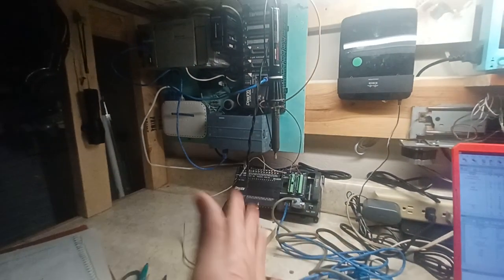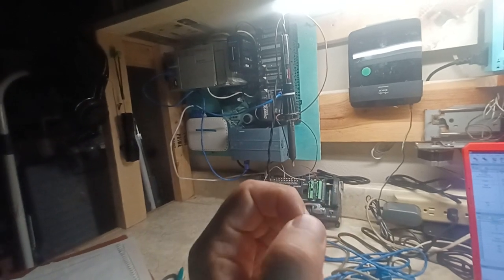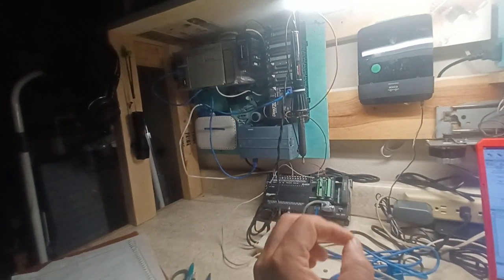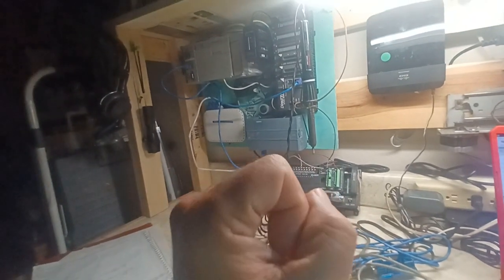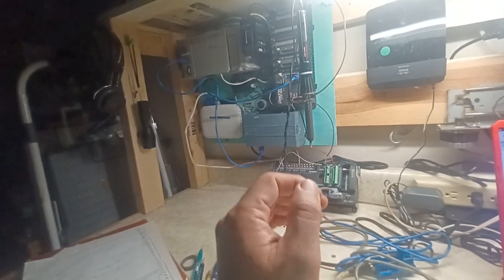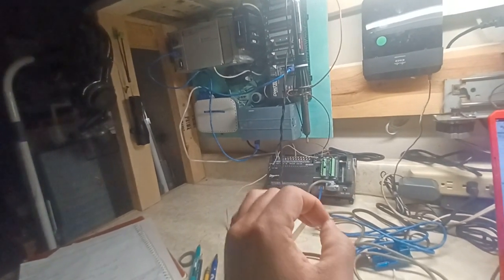So when you tune a system, if you change something in your machine or equipment, if you move your thermocouple or device to a different location, or even change the thermocouple or its wires, you probably need to go back and retune the system because the physical system changed.